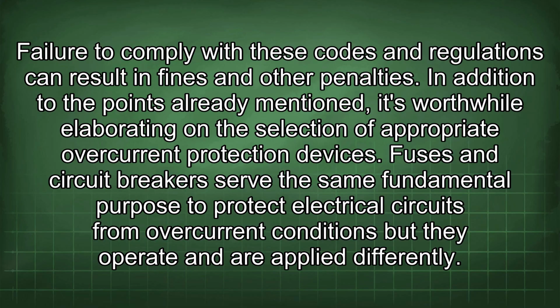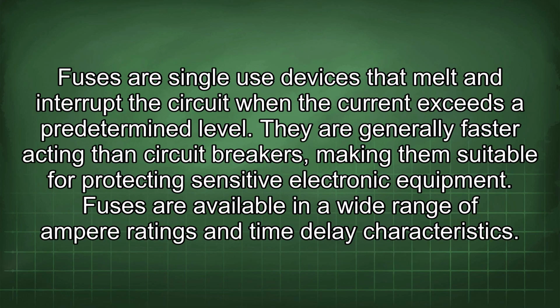In addition to the points already mentioned, it's worthwhile elaborating on the selection of appropriate overcurrent protection devices. Fuses and circuit breakers serve the same fundamental purpose: to protect electrical circuits from overcurrent conditions, but they operate and are applied differently. Fuses are single-use devices that melt and interrupt the circuit when the current exceeds a predetermined level. They are generally faster acting than circuit breakers, making them suitable for protecting sensitive electronic equipment. Fuses are available in a wide range of ampere ratings and time delay characteristics.